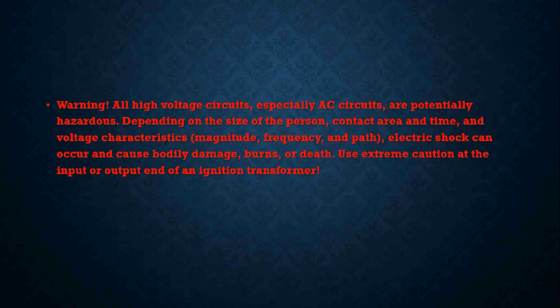Okay, so depending on the size of the person, contact area and time, and the voltage characteristics, the magnitude, frequency, and path, electric shock can occur and cause bodily damage, burns, or death. So you need to be very, very careful and use caution when you are troubleshooting the input and output ends of an ignition transformer.